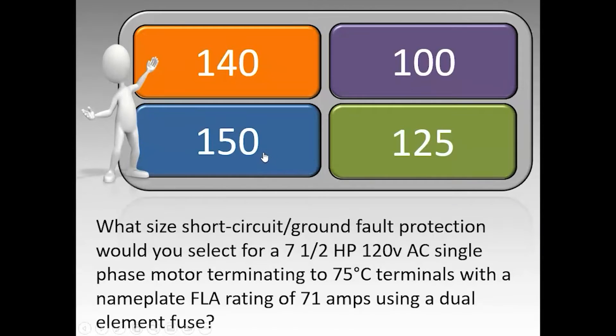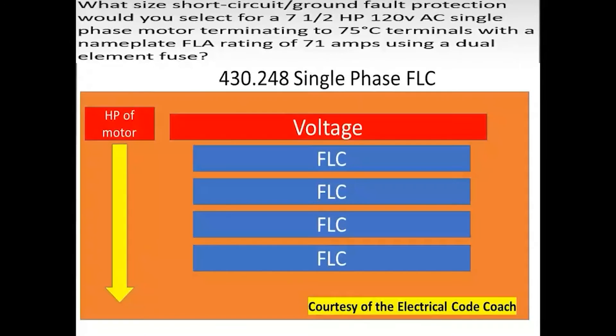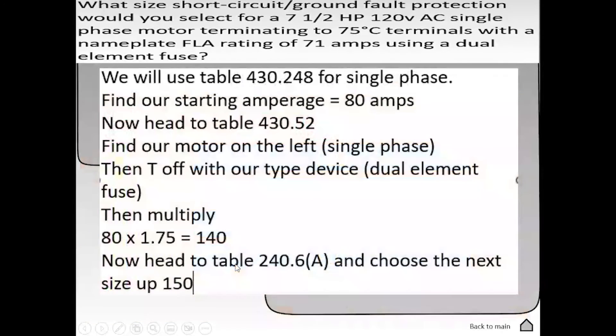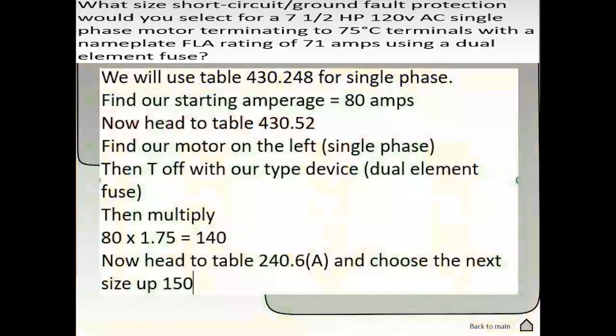The correct answer is 150. For this one, we're going to use table 430.248 for single phase and find our FLC. We start on the left-hand side, find our horsepower, come down and tee off with our respective voltage, and find our FLC, which is 80 amps. Now we head to table 430.52 to find our multiplier. We find our type of motor — single phase — and come across to our type of device, a dual element fuse, giving a multiplier of 175%. We take our FLC of 80 amps multiplied by 1.75, which gives us 140 amps. We head to table 240.6A and choose the next standard size up, which is allowed for short-circuit ground-fault protection. The correct answer is 150.